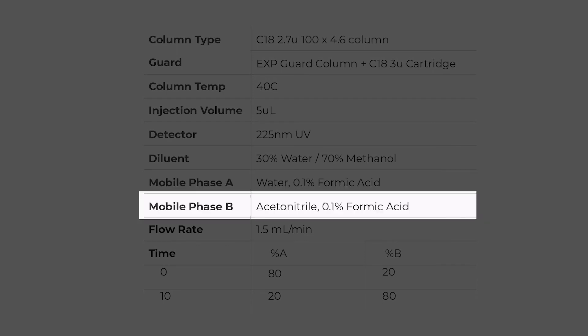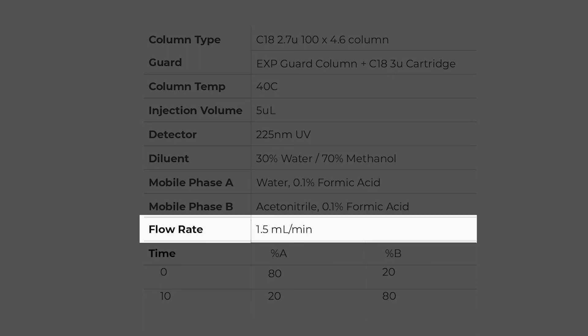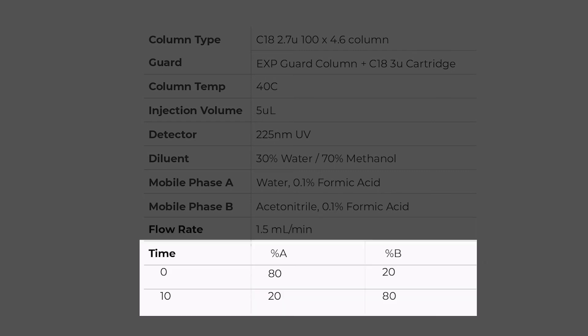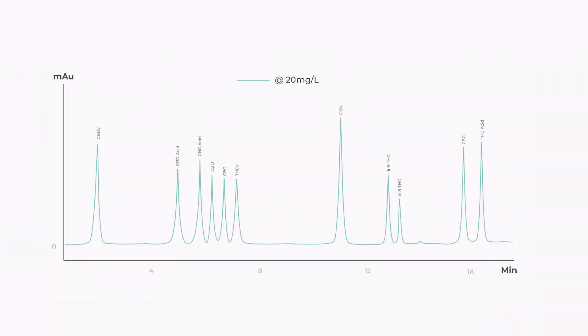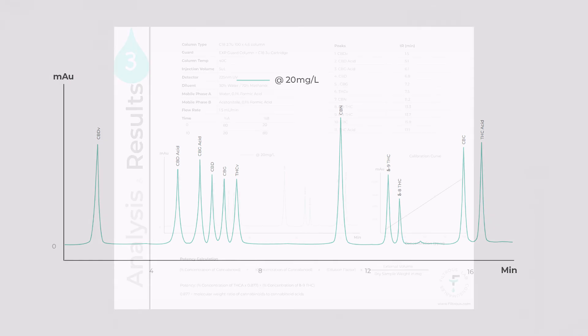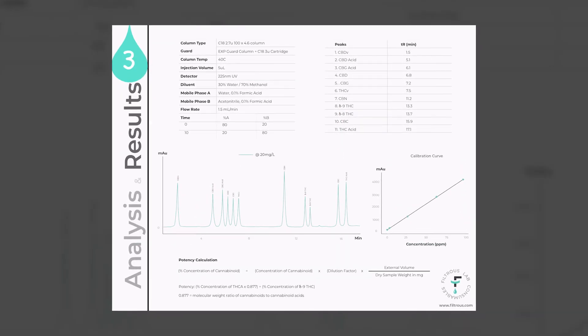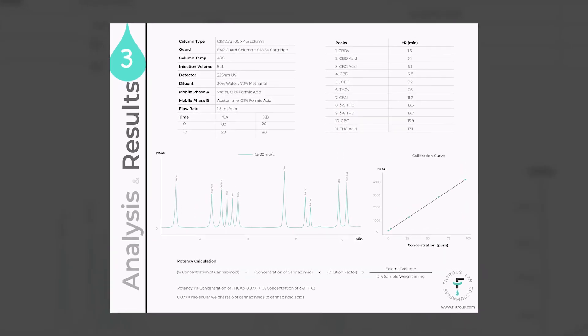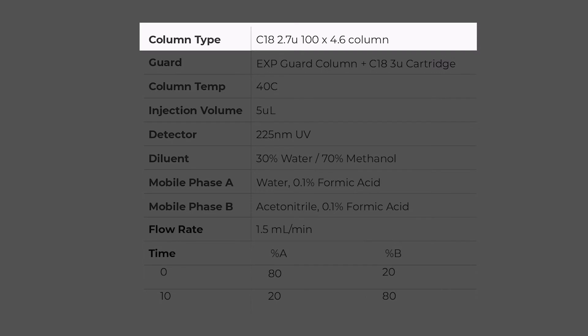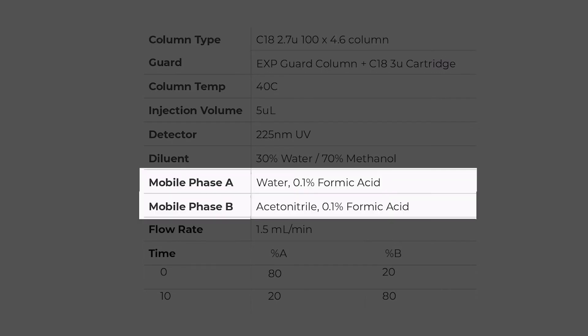The mobile phase A is 0.1% formic in water, and mobile phase B is 0.1% formic in acetonitrile. Flow rate is 1.5 mils a minute and we're doing a gradient. We're starting with 80% A and ramping up to 80% B. These are the typical results for the chromatogram. You may have to do some tweaks, but this is a good starting point. Depending on the type of column that you get, you definitely need to tweak the mobile phase conditions to get the proper separation.